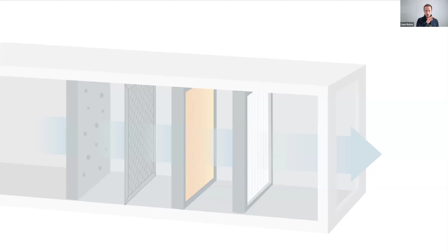Why does this matter? Well, I can understand if my filters are actually performing, right? Are they doing what they're supposed to do? I can do predictive filter maintenance. I can start to see exactly when a filter is beginning to clog, not based on a random calendar date because the manufacturer told you that these filters should always be switched out every 3 months, which, by the way, makes no sense. If I'm using the same filter in New Delhi versus Greenland, those should not be changed on the same schedule. That makes absolutely no sense, right?